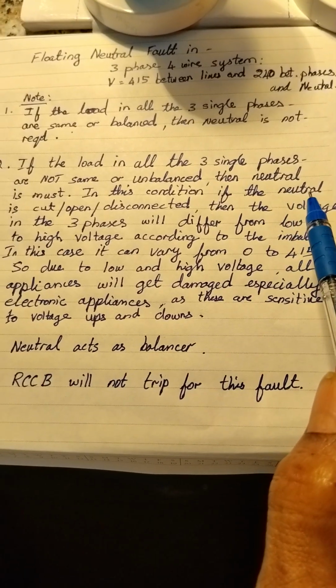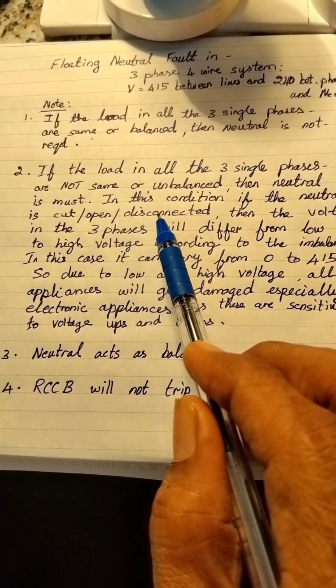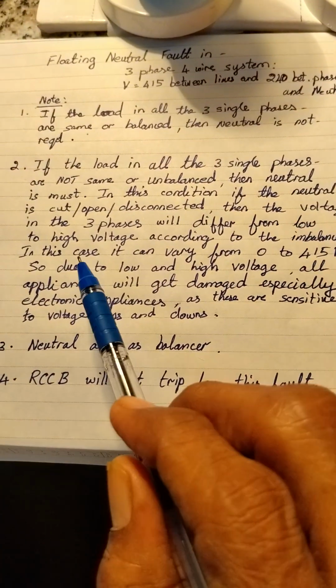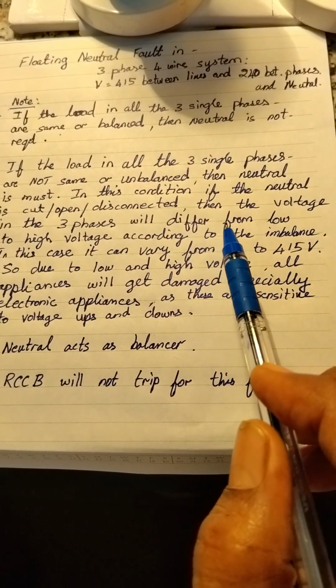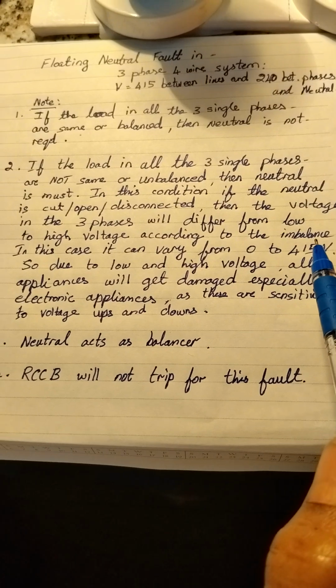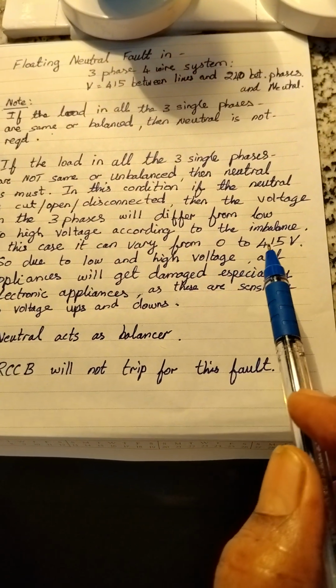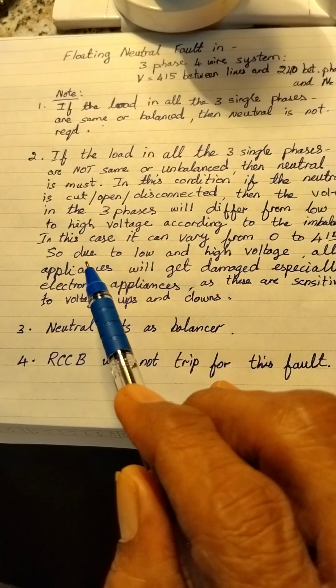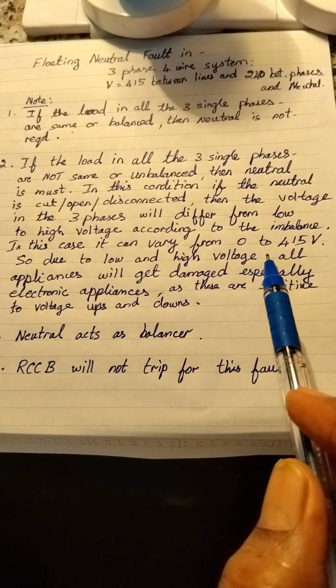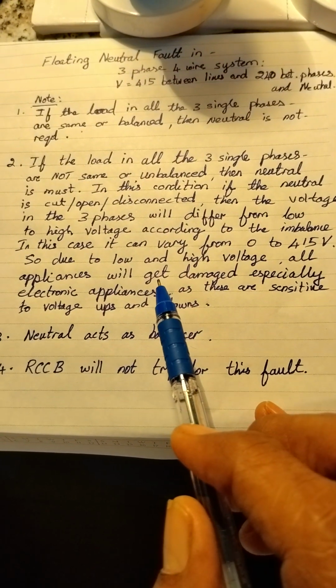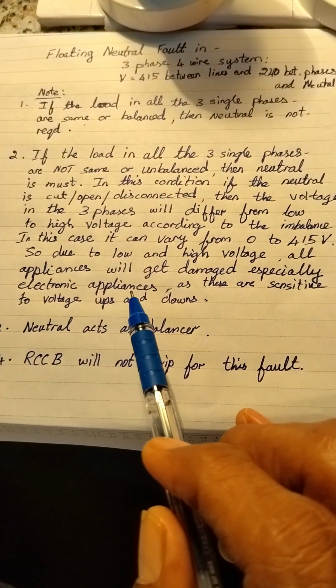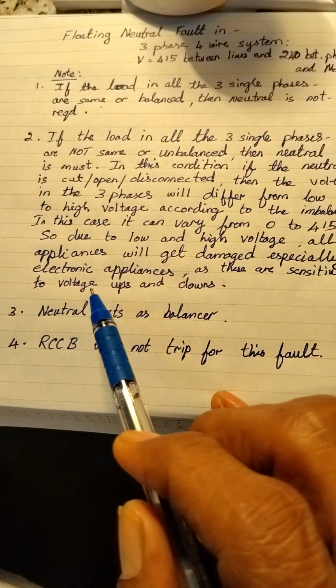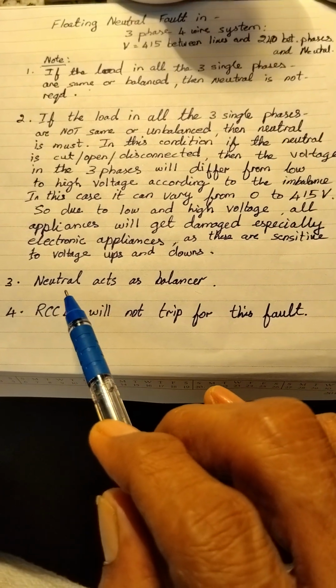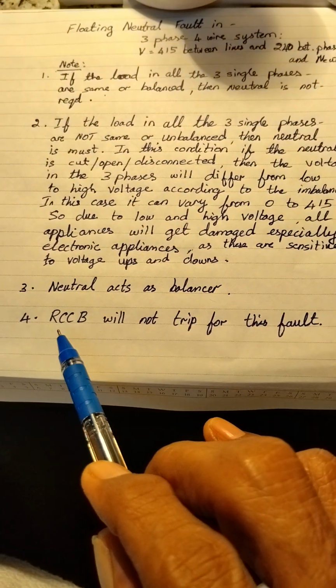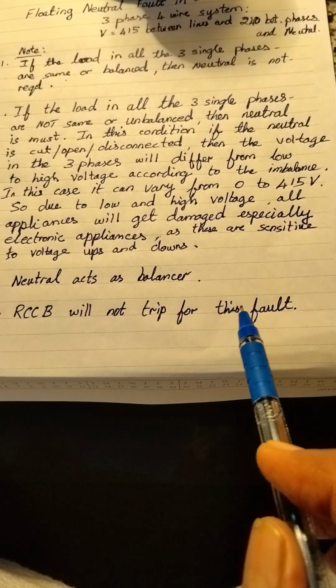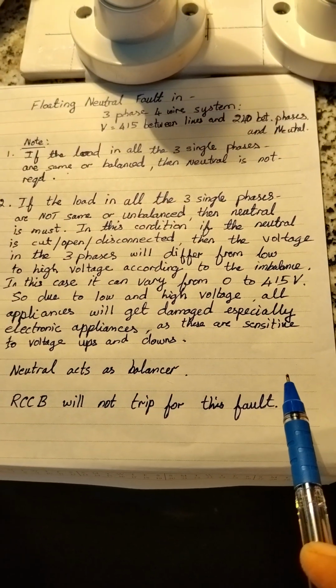In this condition, if the neutral is cut, open, disconnected or loose, then the voltage in the three phases will differ from low to high voltage according to the imbalance. In this case, it can vary from 0 to 415 volts. So due to low and high voltage, all appliances connected to those circuits will get damaged, especially electronic appliances, as these are very sensitive to voltage ups and downs. Neutral acts as a balancer. RCCB will not trip for this fault. So we will go into the demo.